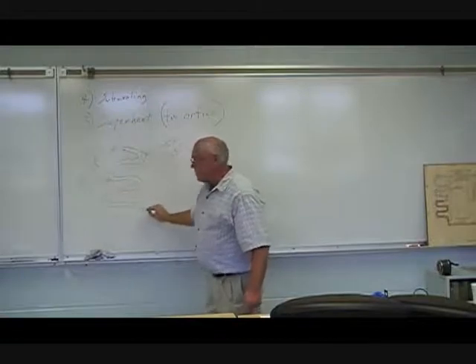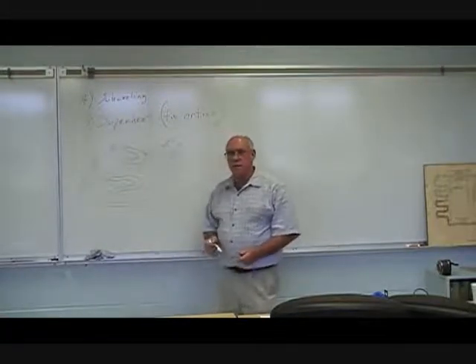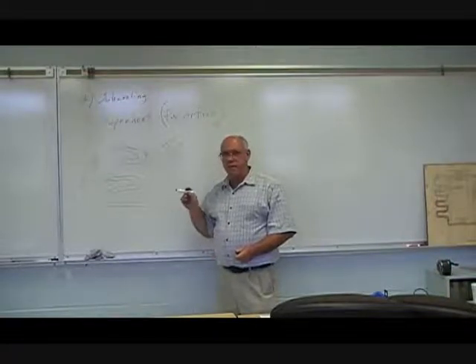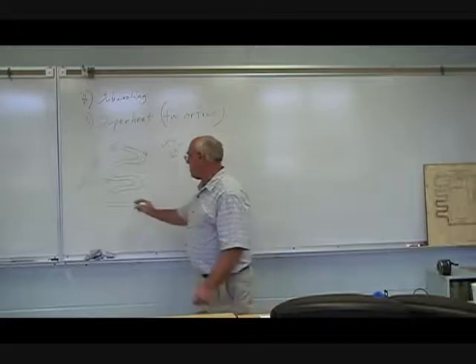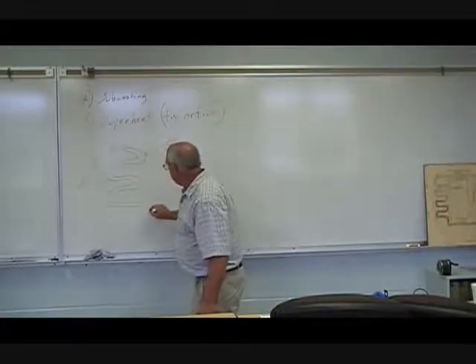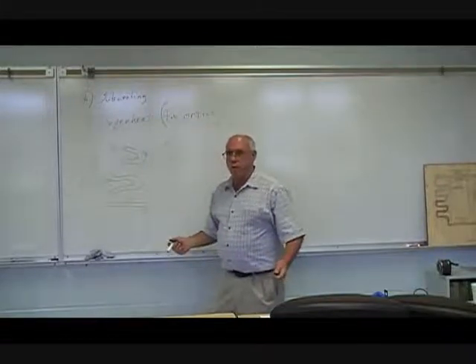The last pass or two, we're going to pick up the superheat. Why do we want superheat? We want vapor. We want vapor going back to that pump. That is a vapor pump, it is not a liquid pump. We talked about what can happen to it. So when it exits the evaporator, we want it to be above the boiling point.